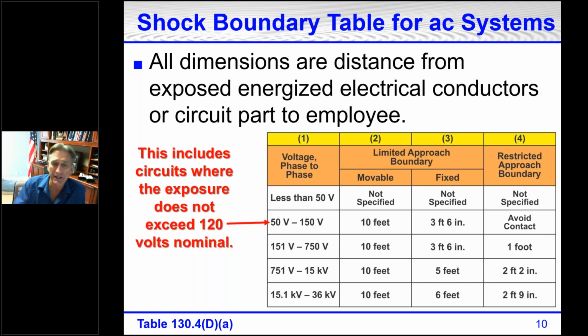So we have a limited approach boundary. For that, we have 10 feet, 3.5 feet, which is the same as the row below that for up to 750 volts. But going all the way to the right, column 4, restricted approach boundary, it says for 120 volts, avoid contact. So as long as you don't touch it, there is really no restricted approach boundary for 120 volts, except don't touch it, avoid contact.